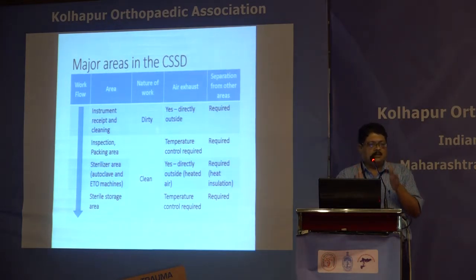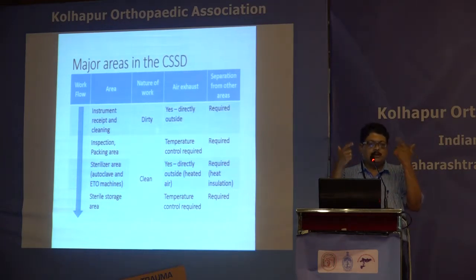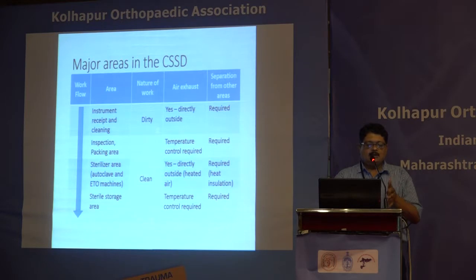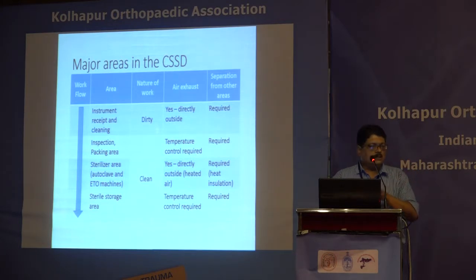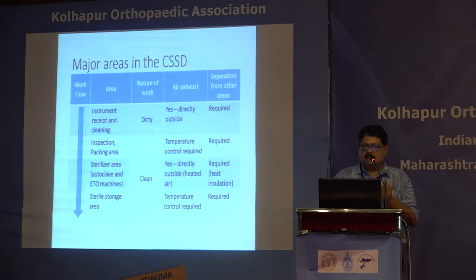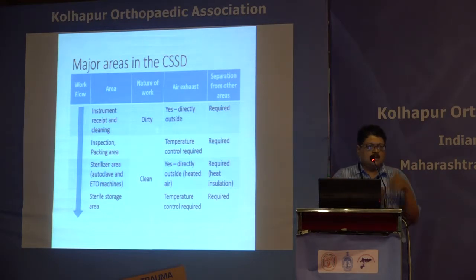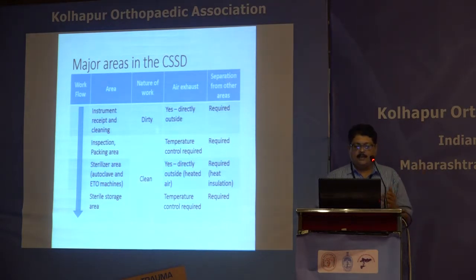The third area is the sterilizer, which must be isolated mainly for heat control — autoclaves operate at 121 to 135 degrees Celsius. Once unloaded, there is a fourth area: sterile storage, where sterile containers, drums, and trays are kept securely away from dust and liquids. Associated areas include a changing room, toilet, and dining room for CSSD staff — similar to the OT complex layout.